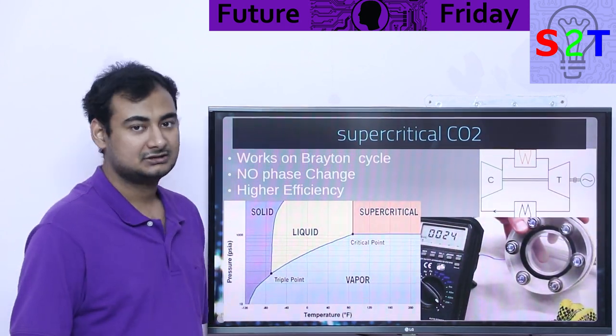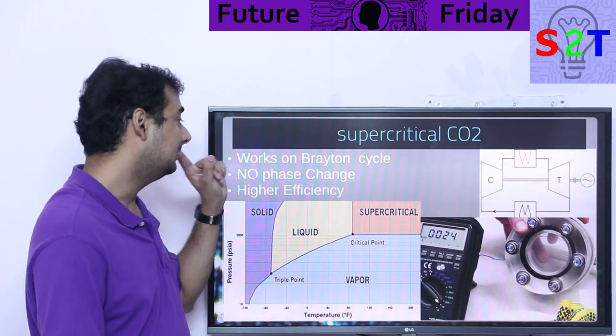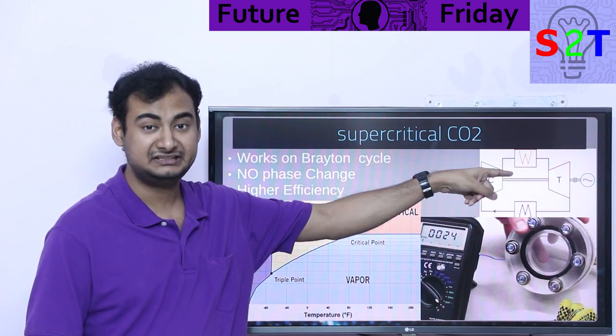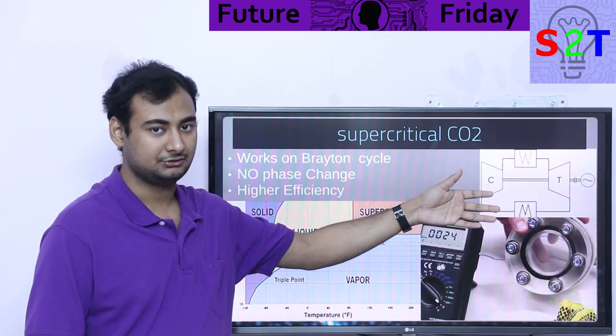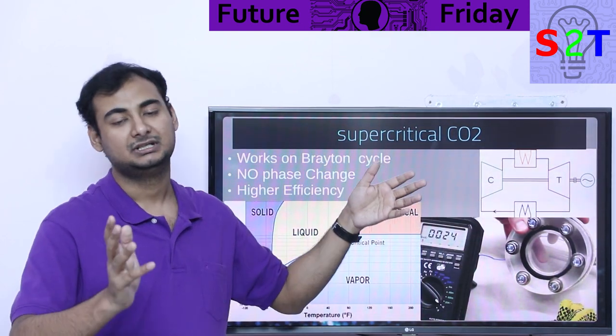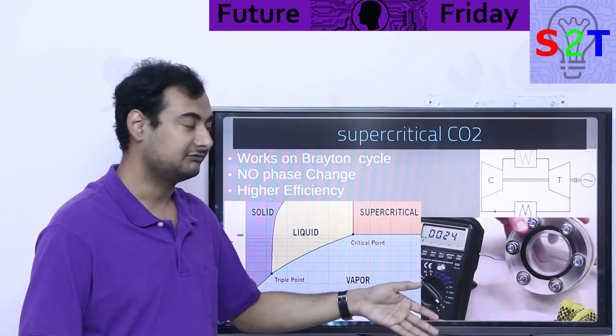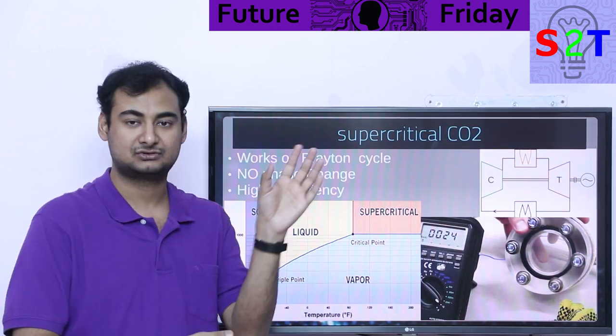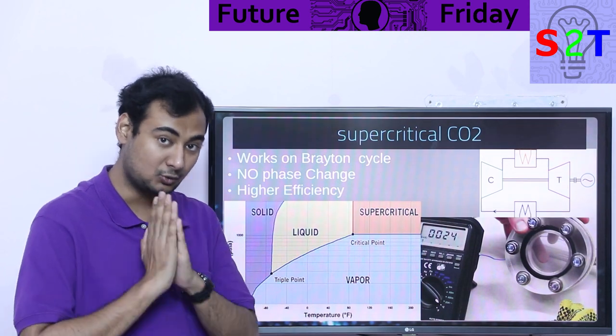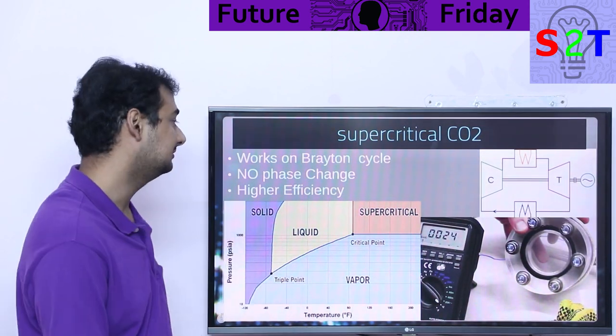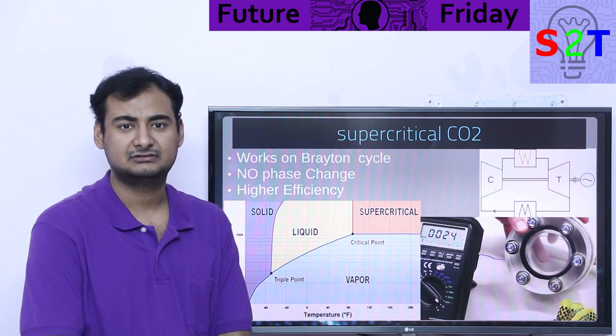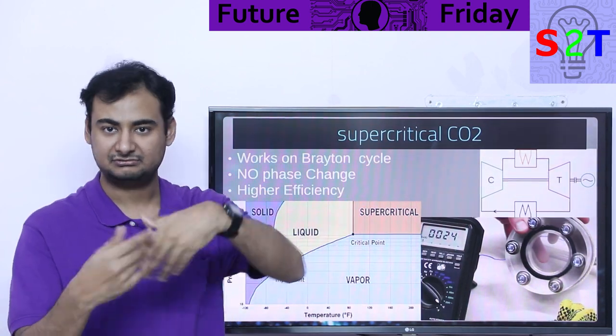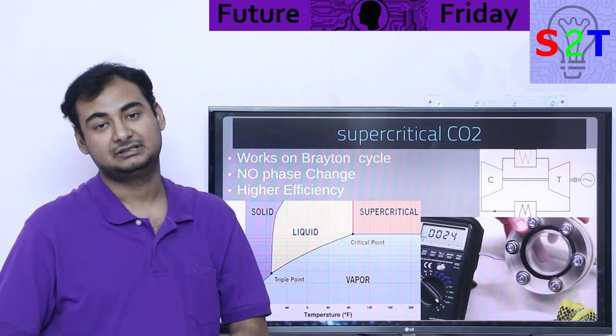Supercritical carbon dioxide works in a different manner — the Brayton cycle. The Brayton cycle has a compressor and a turbine. The turbine does the work, and you have a heat exchanger where you heat it up or cool it down. Cooling it down can use ambient temperature itself. The whole cycle remains in one phase — you do not go from gas to liquid or liquid to gas. The Brayton cycle is also the fundamental thermodynamics of a jet engine.